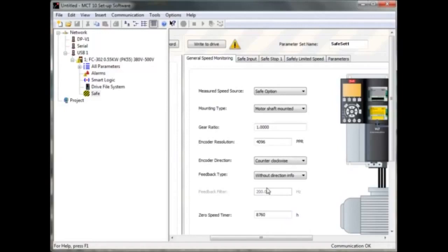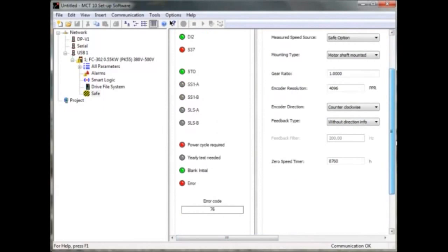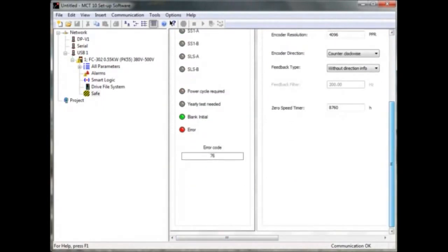For the zero speed timer, leave it at 8760 hours — this means that within one year the drive should run faster than 120 RPM. The error code will also be shown if a failure is detected or no settings have been written into the option.